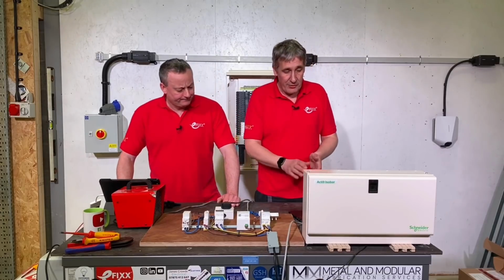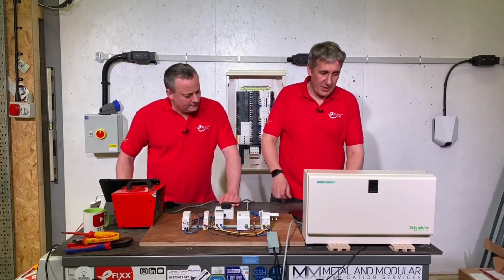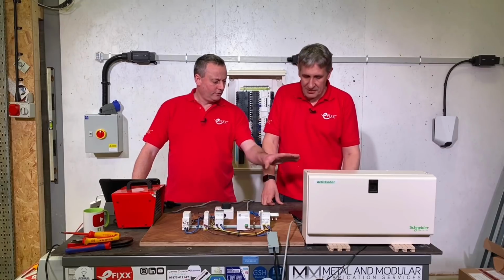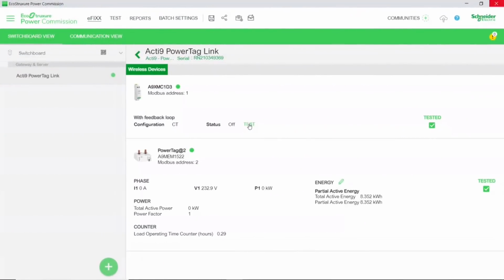First off, I can switch the heater on using the PowerTag - I'll just do that on the screen. So you're switching it on from the computer? Yeah, just bring that in - just press the test button there. You heard the contactor click, now we're being warmed, and you'll start to see the power data coming through on the second line from the PowerTag itself.